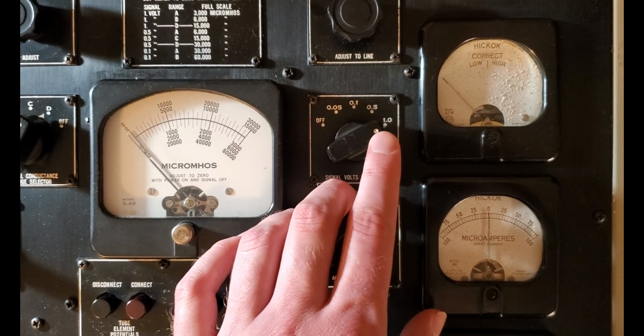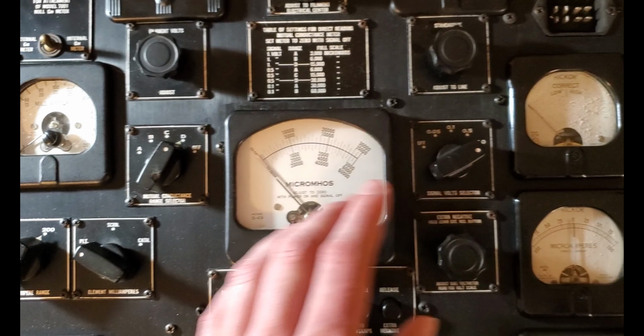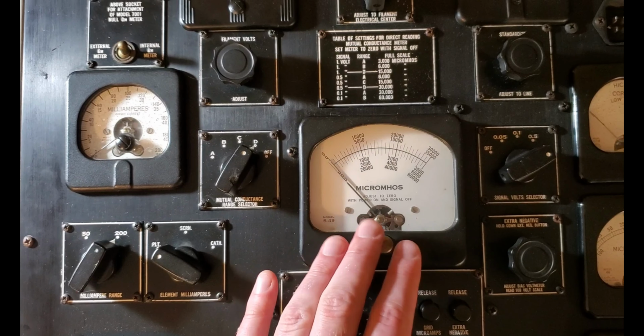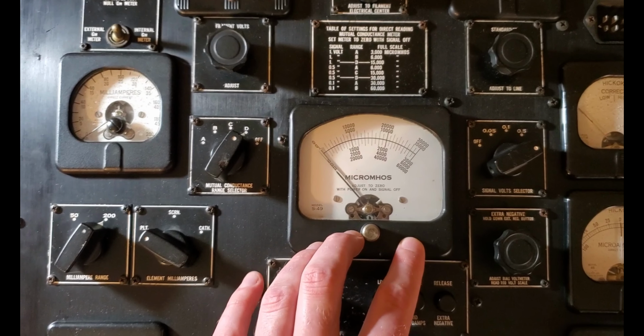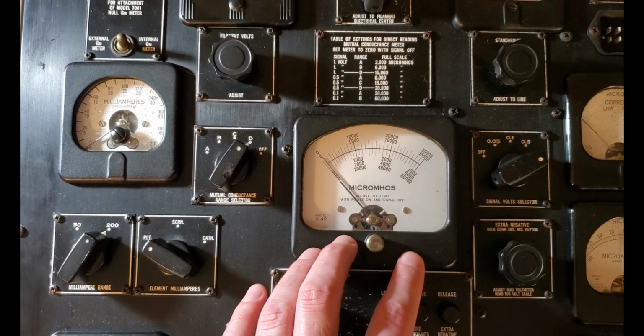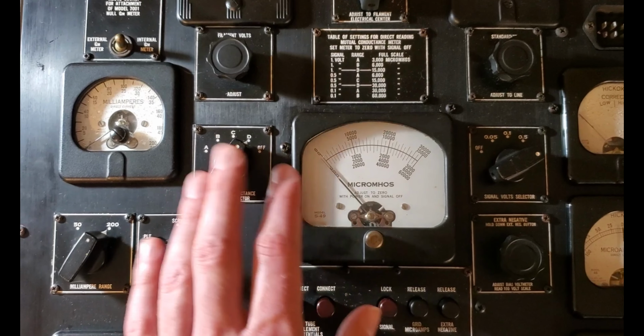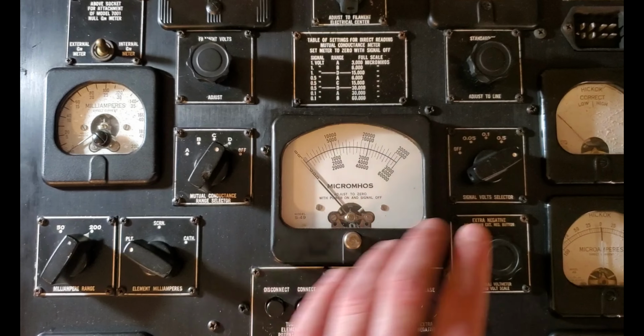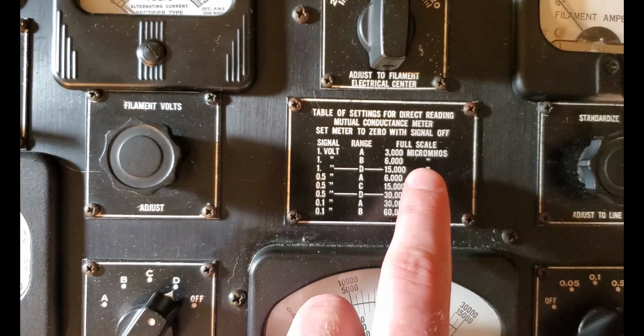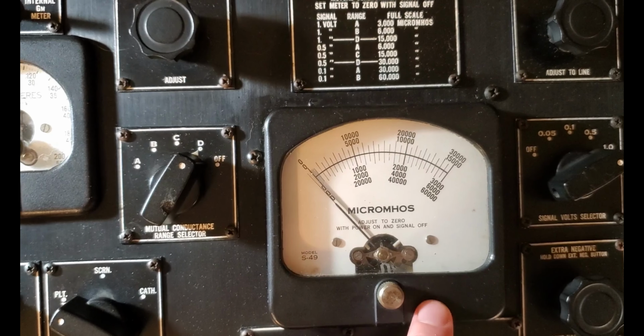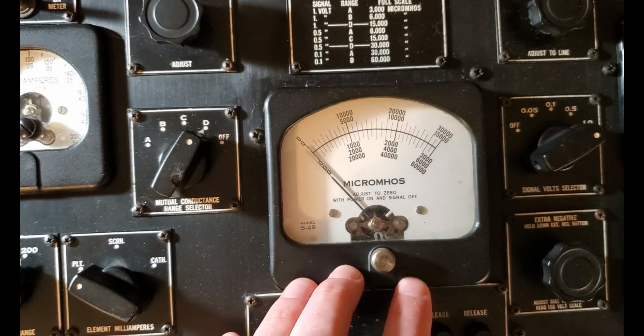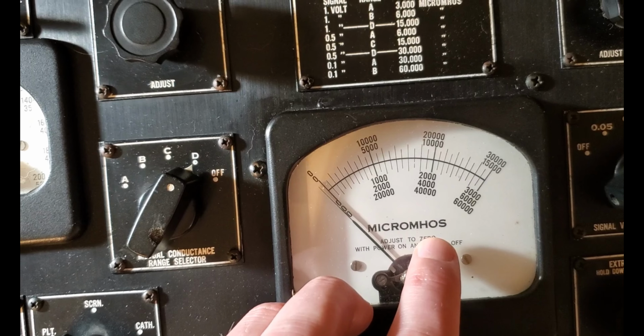So that's adjustable. And as you adjust the grid voltage, you also need to adjust the scaling of the transconductance meter such that you're reading in true micromhos or milliamps per volt. You don't have to do any funny scaling if you change your grid volts. So there's a little plate here that tells you the different combinations of signal volts and that range selector knob over here to get the different full scale in micromhos on this meter. And micromhos, by the way, is just a different name for transconductance.